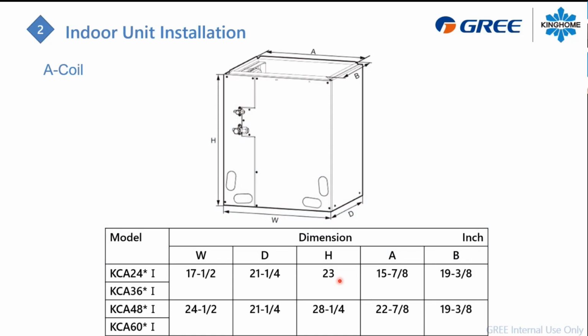So again, you will have your dimension right here. For a 2 ton and a 3 ton case coil, it will be 17 by 21. And for a 4 ton and a 5 ton unit, it will be 24 by 21. So you will have to match your ductwork to be compatible with those width and depth. But if it can fit directly on the furnace, that's a good thing. But make sure you have proper ventilation going through that case coil.